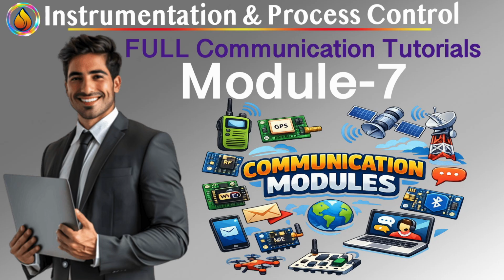Foundation Fieldbus, the core concept, not the marketing version. Let's strip it down to first principles. Foundation Fieldbus was designed to interconnect instruments, actuators, and controllers using a shared digital bus with standardized behavior across manufacturers. The real leap is this: "Control logic no longer has to live in a PLC or DCS." It can live inside the field devices themselves. That single idea changes everything. From centralized control to distributed intelligence.